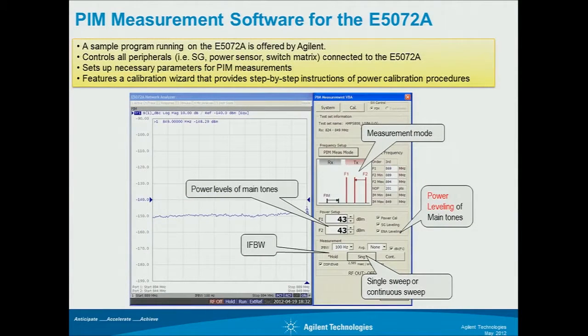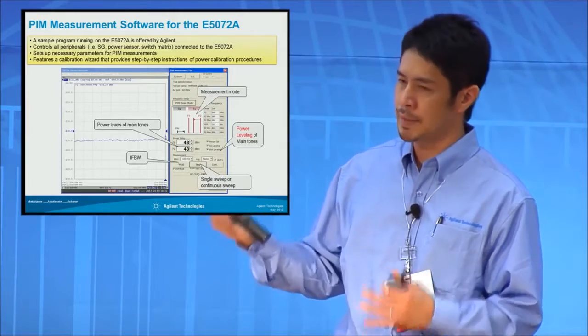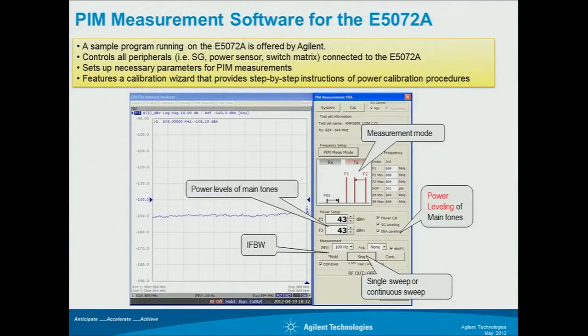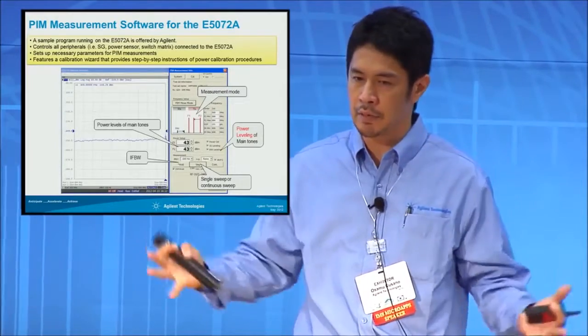Agilent has developed measurement software for PIM measurement and also S-parameter measurement. This is a program that users can download from our website, and you can use it for free. This software controls all peripheral instruments like the signal generator or power meters. It supports several measurement modes, you can change the power, adjust the IF bandwidth to change noise and speed, and it supports all calibration steps to calibrate the full configuration.